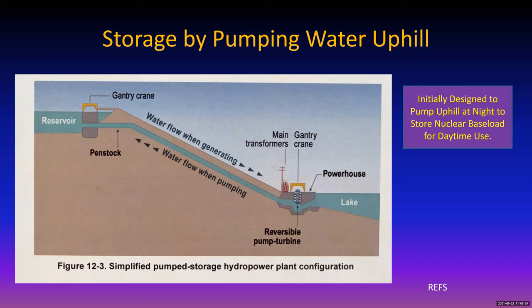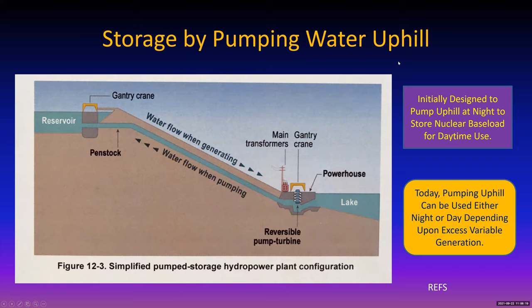Now, as the mixture of wind and solar becomes higher and higher, it's highly likely that these storage systems will start pumping water uphill during the day when the sun is shining, and using it to flow downhill at night to meet the nighttime load. So who would have guessed 50 or 60 years ago that these things would be running backwards in the 2020 timeframe? It all depends on when you have excess generation, whether you want to pump uphill or downhill. Time-wise, it takes about a half an hour to switch over from pumping uphill to pumping downhill.